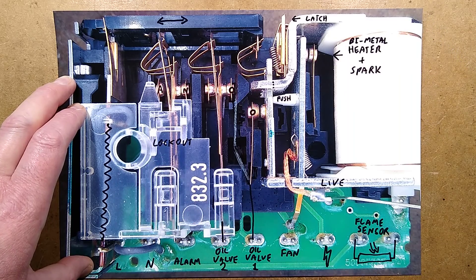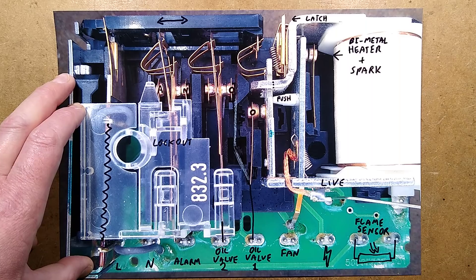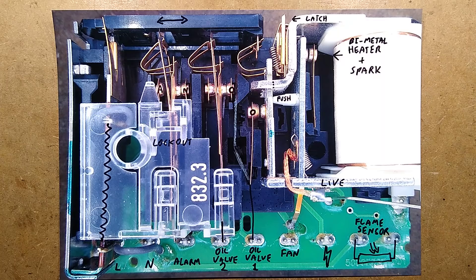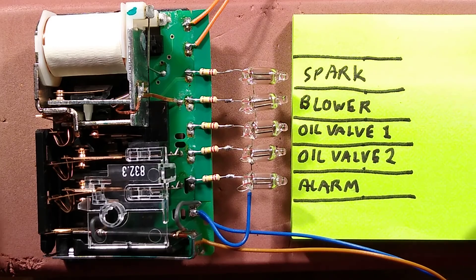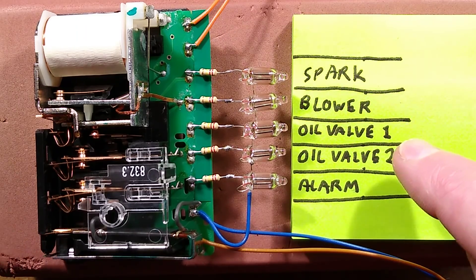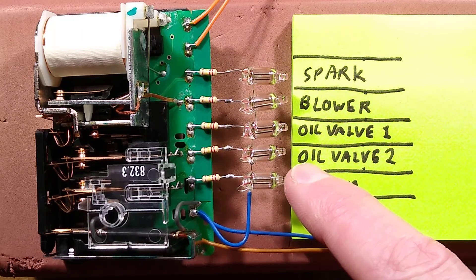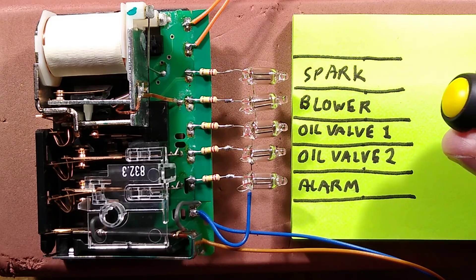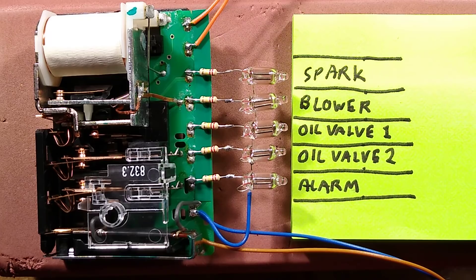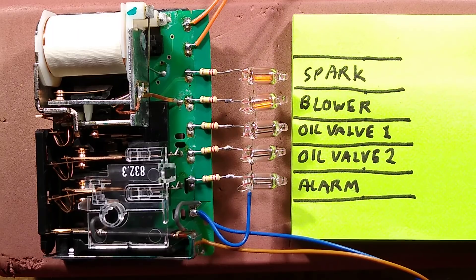Right, now I'm going to show you the thing actually operating. To show operation, I've connected five neon indicator lamps: the spark, the blower, which is powered all the time as long as this thing is powered, oil valve one, oil valve two, and the alarm neon. To emulate the spark being lit, I've wired a little button across it. So at the correct point in the sequence, I shall push this button and it will indicate the spark has occurred. It is now active.